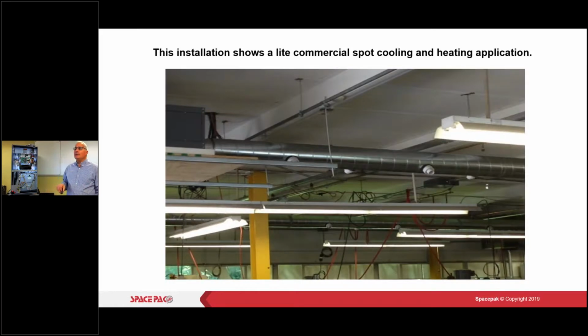And then we do have the ability to do some spot heating and or cooling. This is what we're showing you here in a commercial application. I don't even need the 2-inch drops. So if this is a noisy assembly area or what have you, I can just take some outlets right off of the plenum and use spot cooling. We've done that in some automotive dealerships in their garage areas, spot cooling.